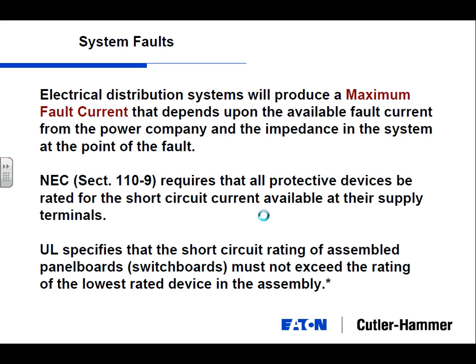So I touched on this. The electrical distribution system will produce a maximum fault current that depends on the available fault current from the power company and the impedance in the system at the point of the fault. So every building is going to have a different maximum fault current. And when you construct a building, the utility will come in and they'll give you the power. And utility will be responsible for telling you the maximum fault current at this point is 65,000 amps, or whatever that is. And what are some of the factors that come into play for them? How far are you from a transformer? How far are you from a generating station? How many other customers may be on this same grid that you're on?